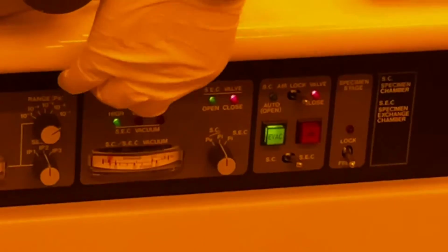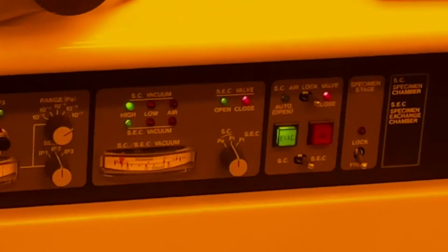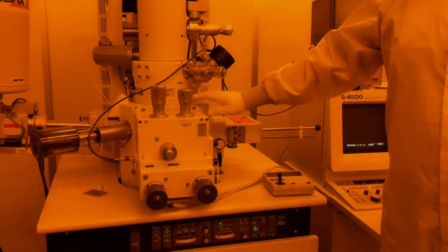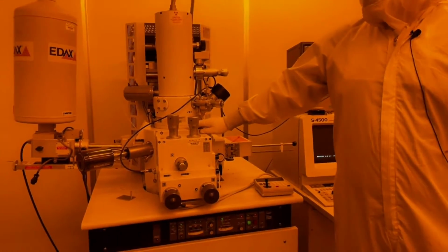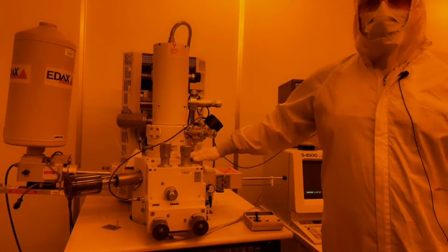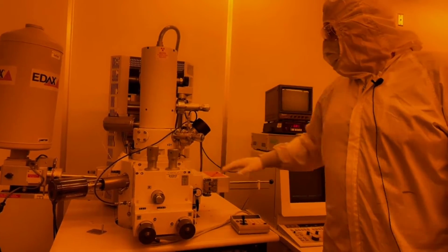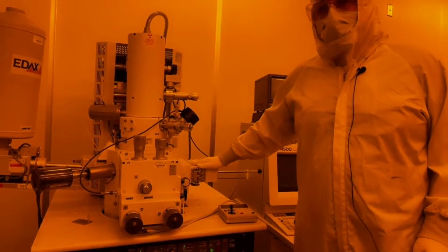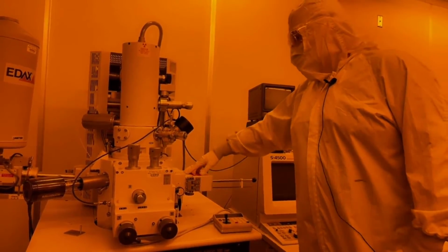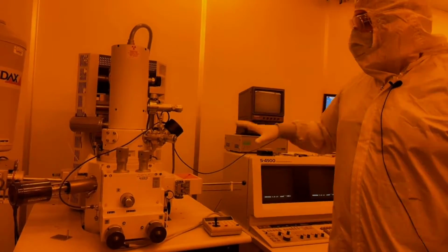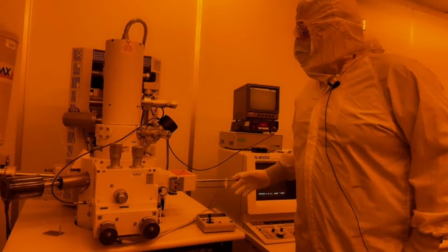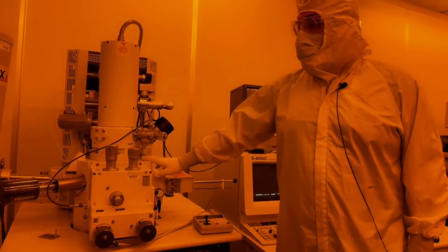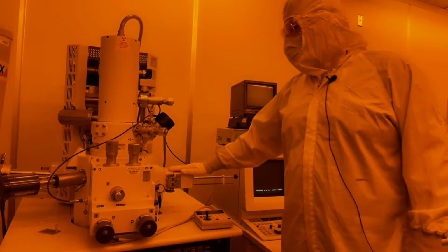Next, we have the vacuum for the main chambers. So we have 2 main chambers here, plus our gun chamber. We have the sample chamber, SC. This is where you place your sample to be imaged. You have the sample exchange chamber, SEC. This is a load lock, basically, so you can put your sample in here and then transfer it into the main chamber once the load lock is at a proper vacuum.